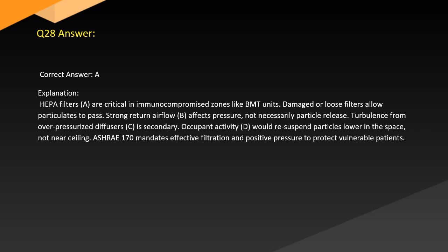Answer. Correct answer: A. Explanation. HEPA filters are critical in immunocompromised zones like BMT units. Damaged or loose filters allow particulates to pass. Strong return airflow (B) affects pressure, not necessarily particle release.